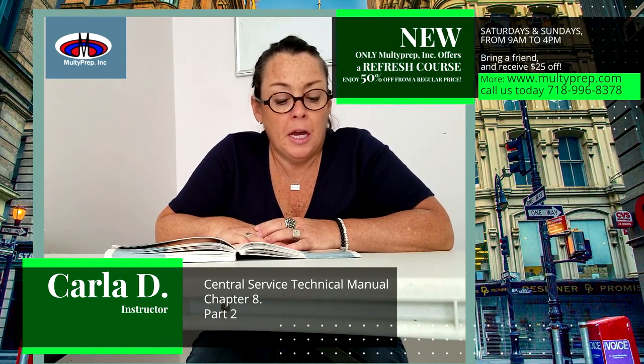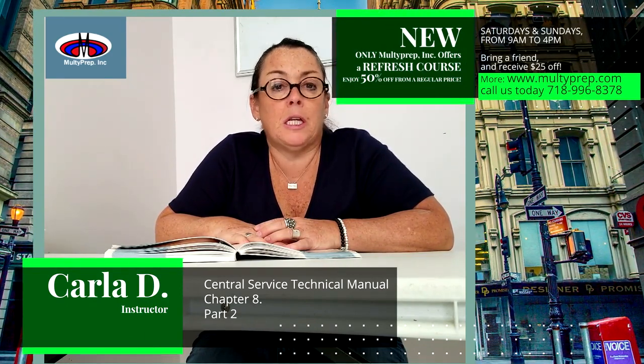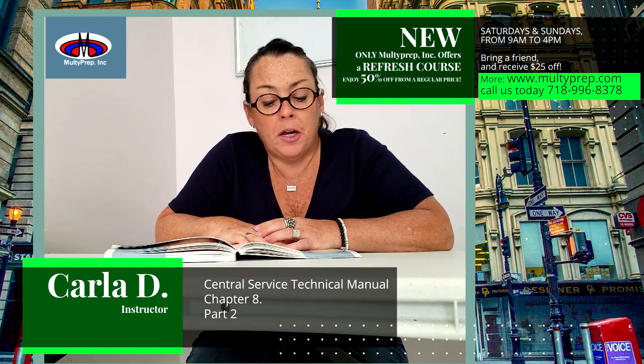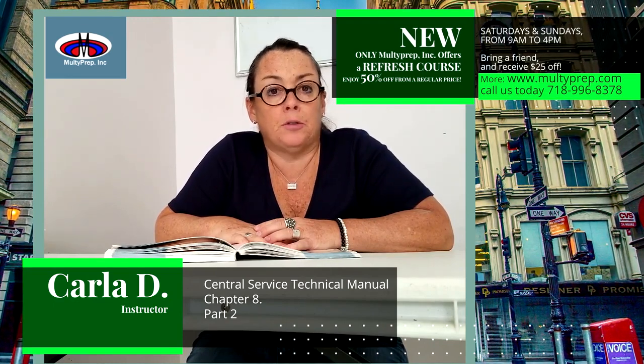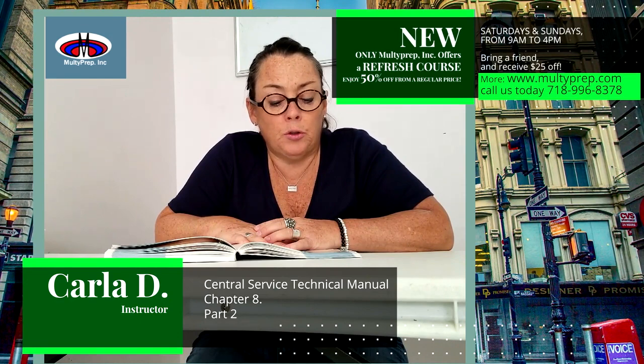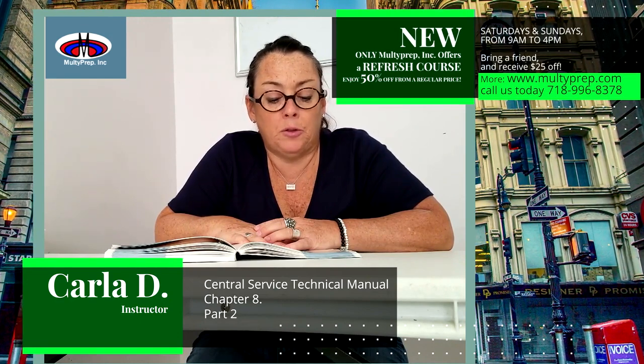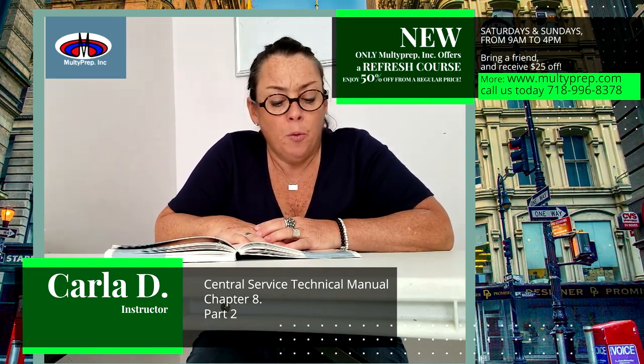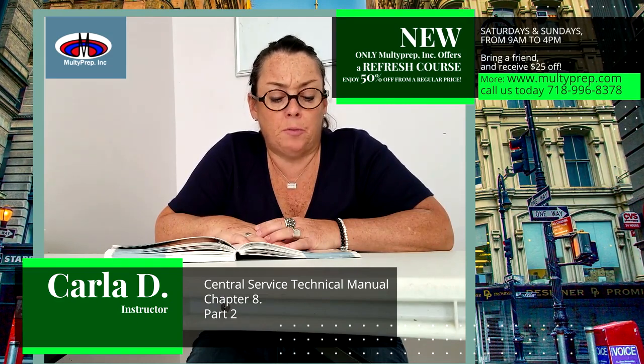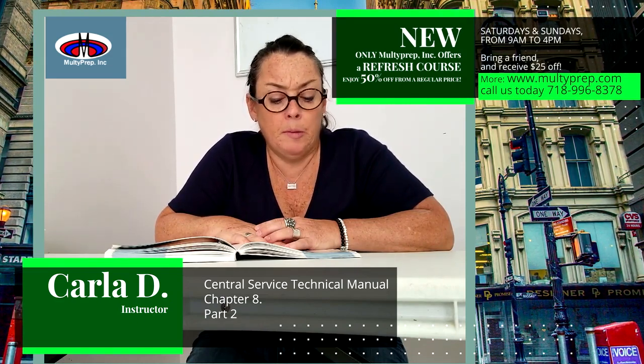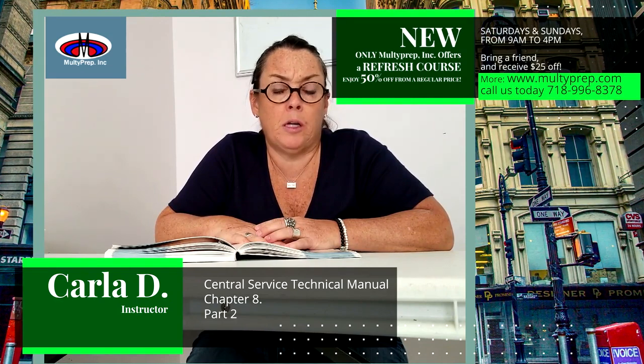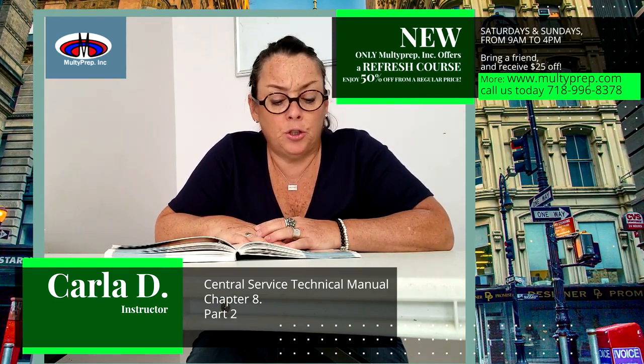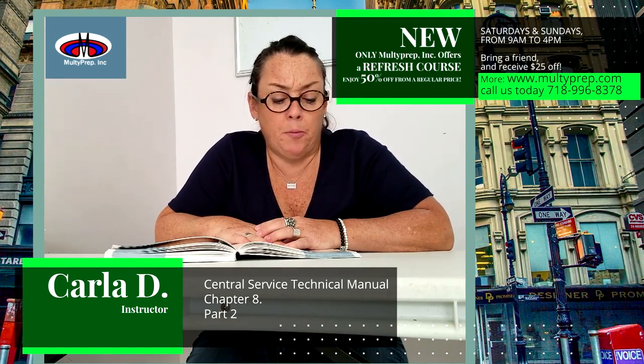Instrument cycles generally are the longest cycles because they have multiple rinse, wash, lubrication, and drying times to meet the instrument's cleaning needs. Basins and containers are generally run on a utensil cycle. Some washer manufacturers offer special cycles for delicate instruments. When running a mixed load of containers and instruments, the instrument cycle should normally be utilized for maximum cleaning.